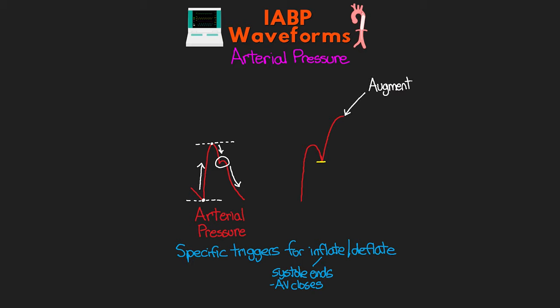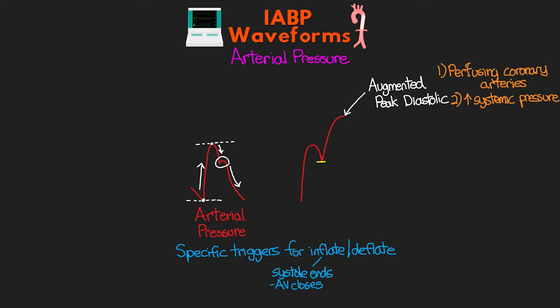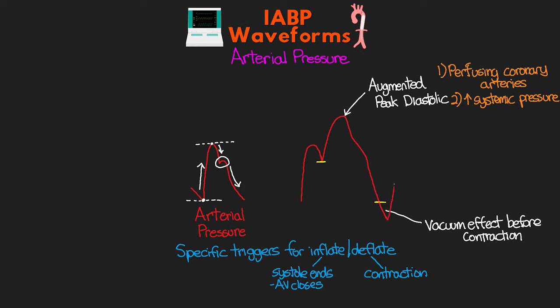The arterial pressure will rise until the balloon is fully inflated, and this is our augmented peak diastolic pressure — what you see shown as augmentation in white next to the balloon pressure waveform. Think of this as the increase in pressure that is, one, perfusing the coronary arteries, and two, increasing the systemic pressure. This augmented waveform appears as the highest point on the pressure tracing. From there, the same diastolic runoff occurs as arterial pressure drops. The next trigger is when the heart begins to contract — this is when the balloon deflates, creating a quick drop-off in pressure and a vacuum effect to reduce afterload just as the heart is beginning to contract again.